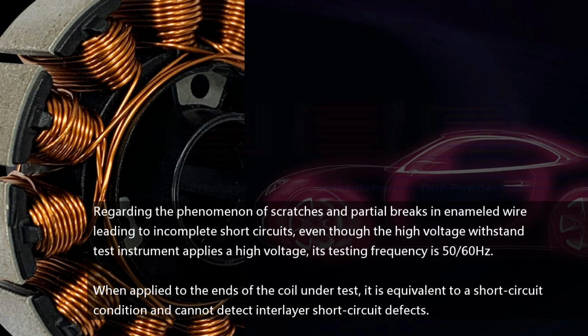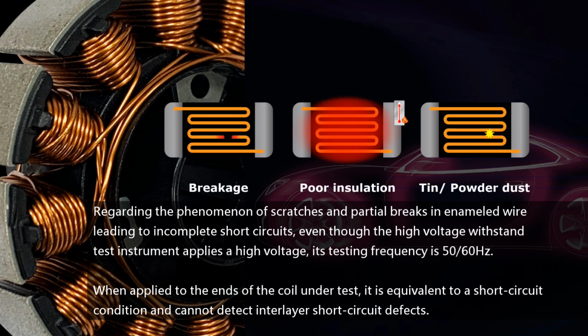Despite the high test voltage of the insulation tester, its testing frequency is 50/60 hertz. Applying it to both ends of the test coil is equivalent to a short circuit condition and cannot detect interlayer short circuit defects in the product.